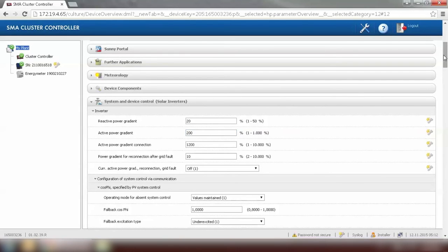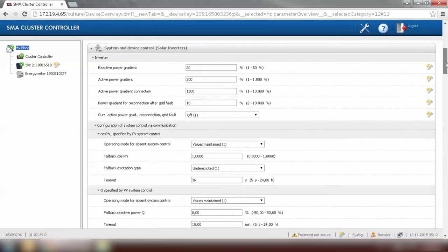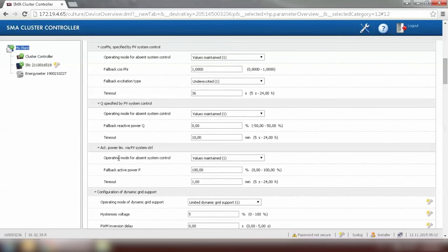Okay. The last parameter we need to set is the fallback on the active power limitation via PV system control, and set the operating mode to use fallback settings, and set the fallback active power to zero, which means if the inverter loses communication to the energy meter or the cluster controller, after 1 minute, it will go to fallback and produce zero power.